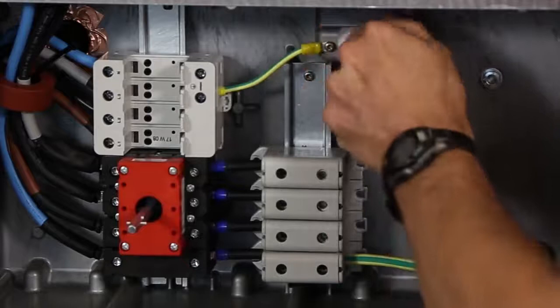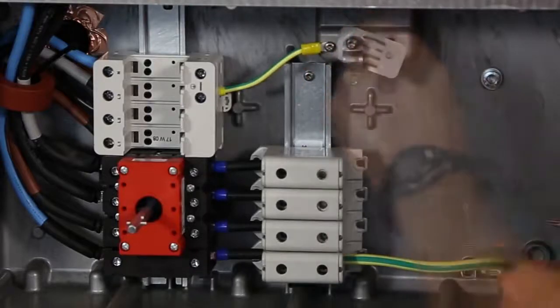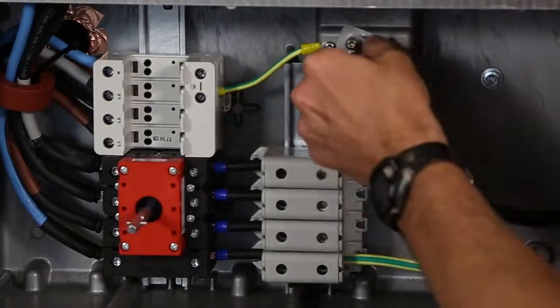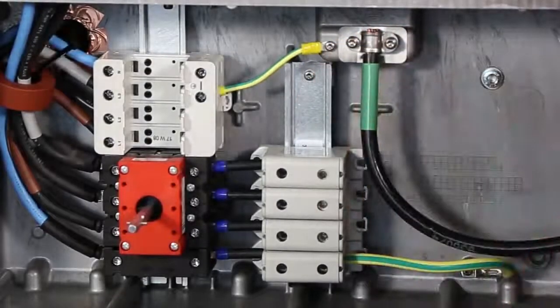First we proceed to the installation of the AC wires. For this process we will need both a Torx 30 and a Torx 25 screwdriver. First, bring the equipment ground conductor and attach it to the PE grounding point just above the AC wiring block using the Torx 25 screwdriver to secure the clamp.